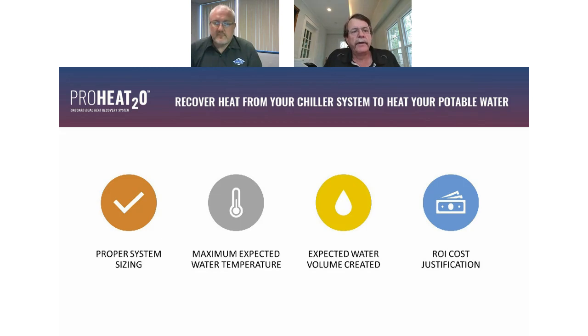There are a lot of competitors out there that make claims about how much heat you can recover. The maximum you'll ever get is the temperature of the refrigerant, which in most cases is 160 degrees. But in reality, with line loss, temperature change, and operating time, we think a safe number to talk about is 140. So you'll never see us quote energy or heat recovery greater than 140 degrees.